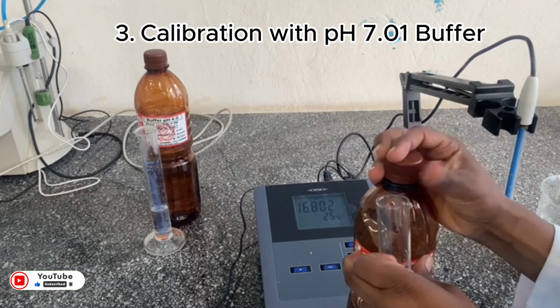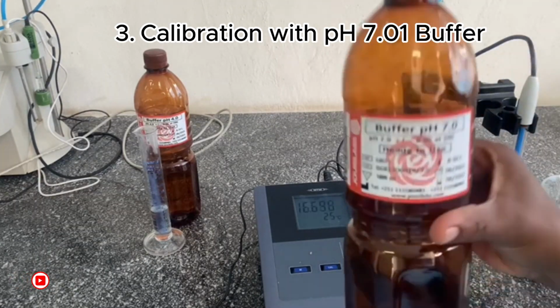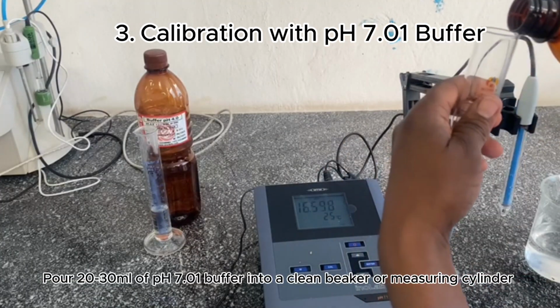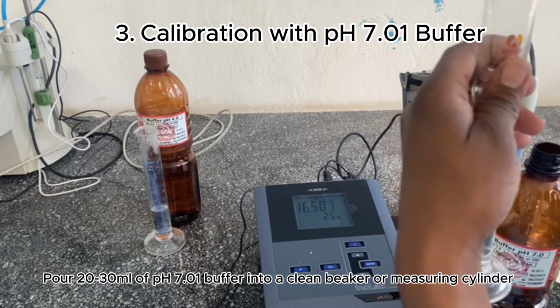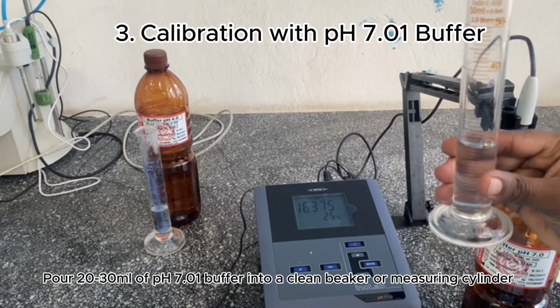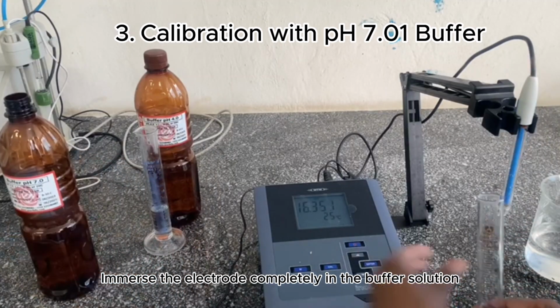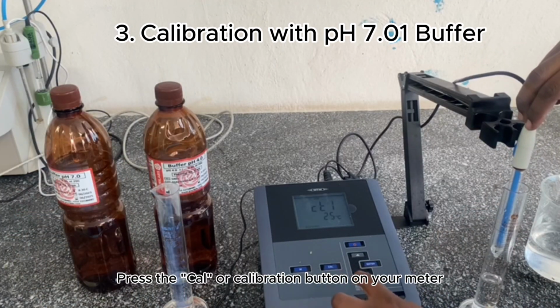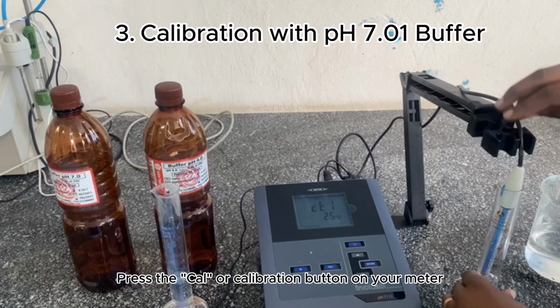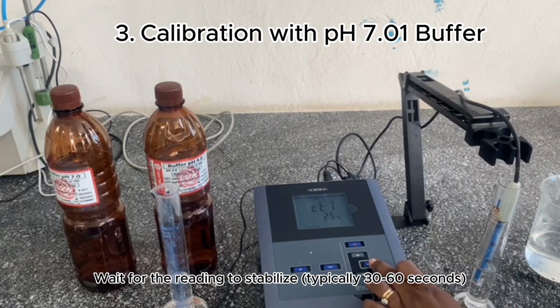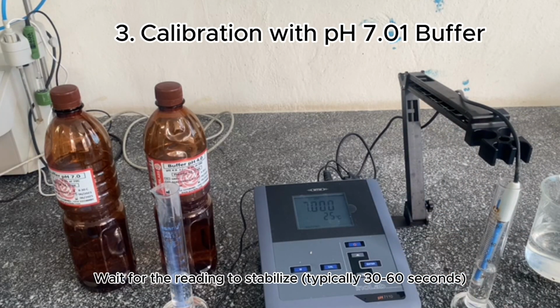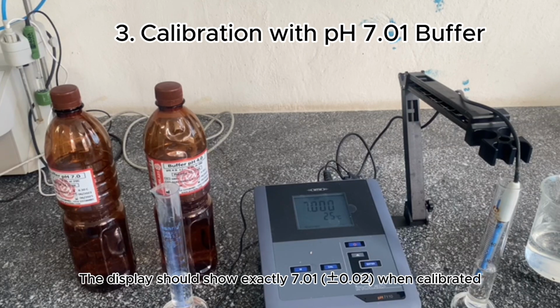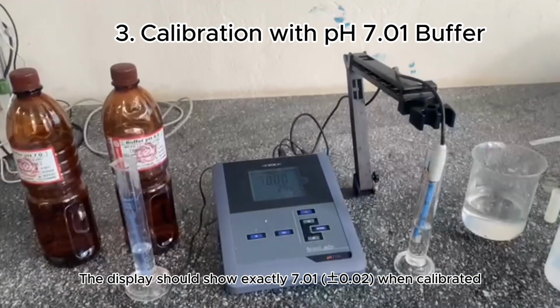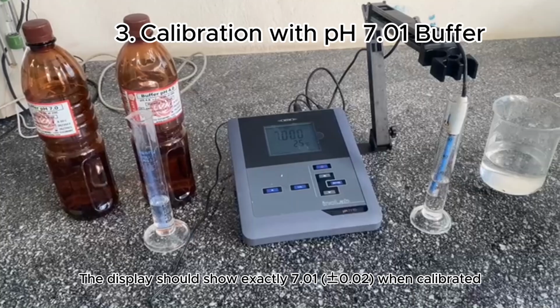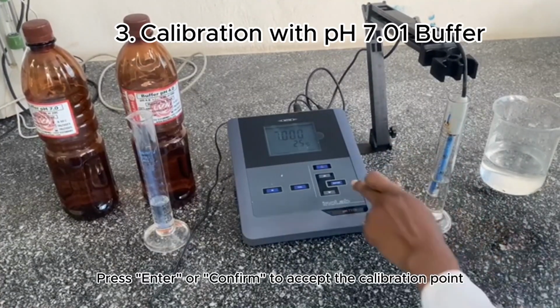3. Calibration with pH 7.01 buffer. Pour 20 to 30 milliliters of pH 7.01 buffer into a clean beaker or measuring cylinder. Immerse the electrode completely in the buffer solution. Press the Cal or calibration button on your meter. Wait for the reading to stabilize, typically 30 to 60 seconds. The display should show exactly 7.01, plus or minus 0.02, when calibrated. Press Enter or Confirm to accept the calibration point.